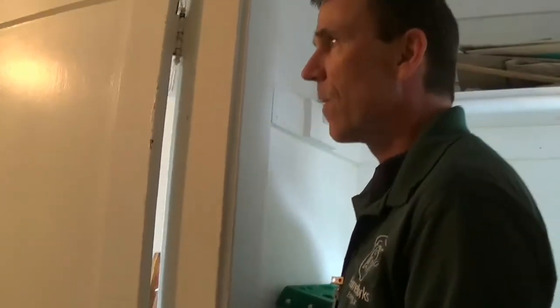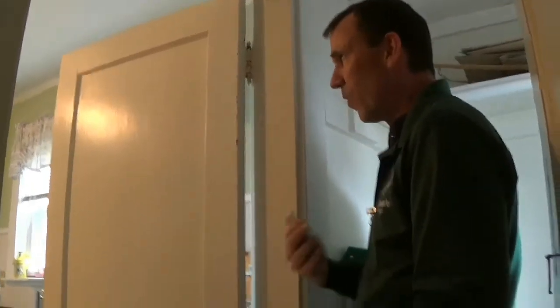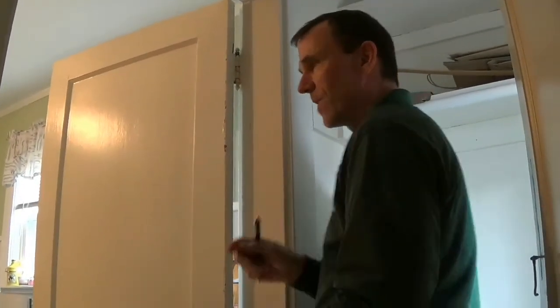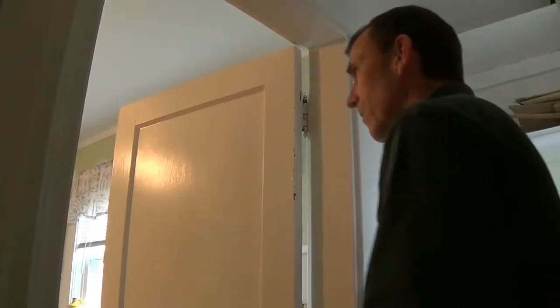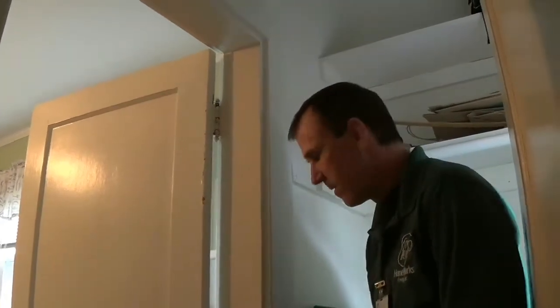One of them's up here. It's this kitchen exhaust fan. And we also have a clothes dryer downstairs, which we've already turned on. And we're going to see which one of these exhaust fans is winning the battle. What is making the worst depressurization for the combustion appliance zone. So that's why I back myself into the combustion appliance zone, and I'm figuring out which one of these doors has to be open or closed as I'm backing my way into the combustion appliance zone. All right, so come on back down this way. Uh-oh.